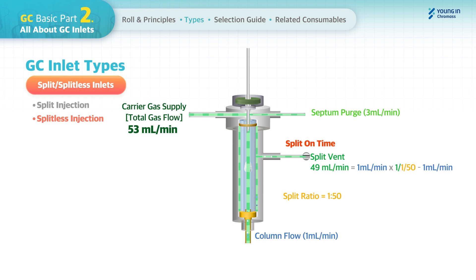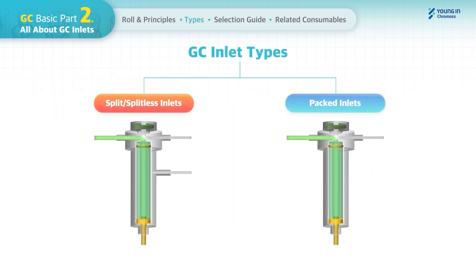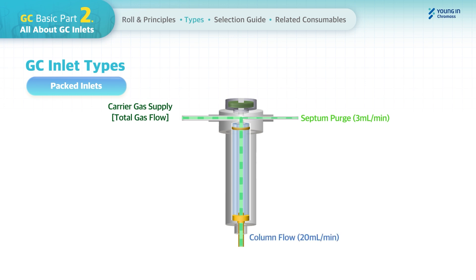The packed column inlet design is simple: the entire carrier gas enters the column after subtracting the septum purge flow. For example, if column flow is set to 20 mL/min, the total will be 23 mL/min. After gas flow stabilization, the sample is introduced to the inlet liner and the entire sample is loaded into the column. Depending on the GC manufacturer, the septum purge line may not be available.